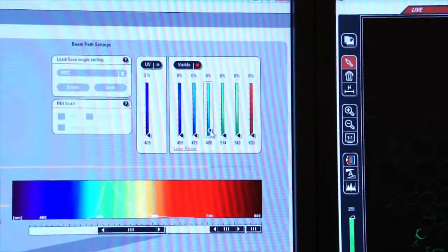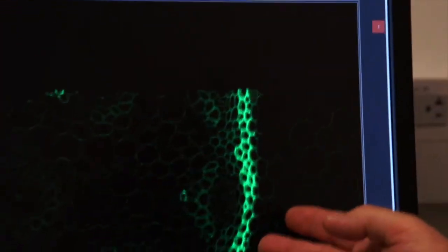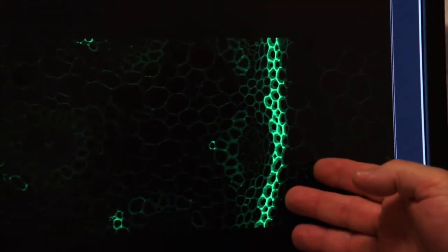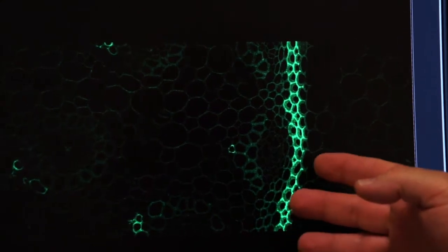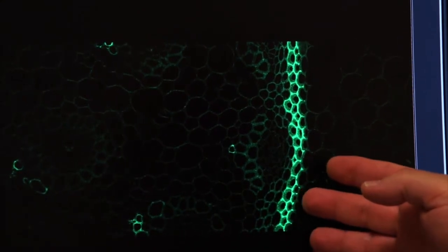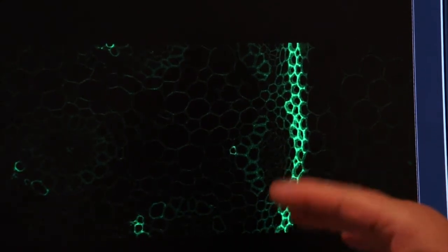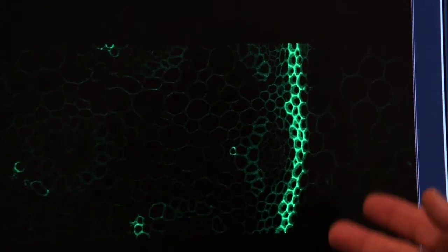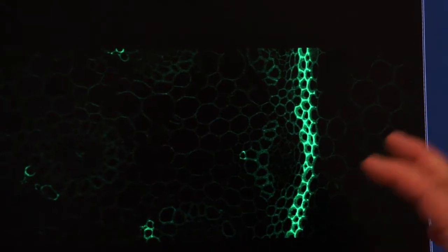I can always lower my laser if you look over under the visible laser tab. I can lower the power of the laser by sliding this bar down a little bit. And you can see that instantly my image dims because I've lowered the laser power. So, it's always a good idea to keep your laser power low if you can.